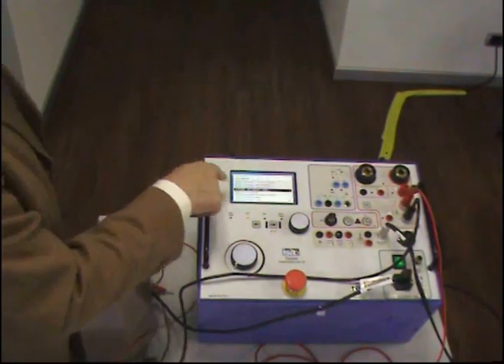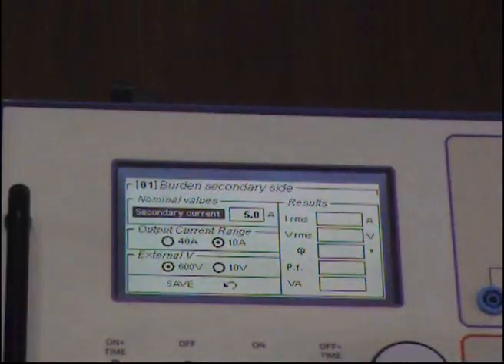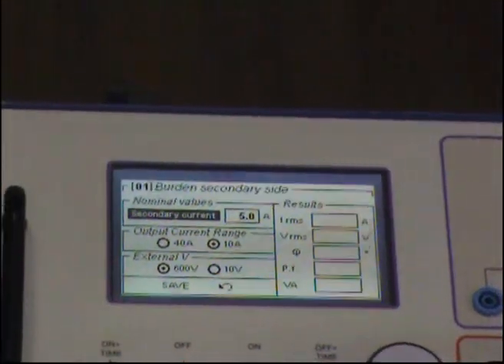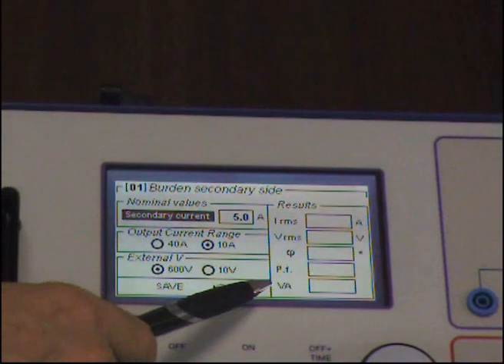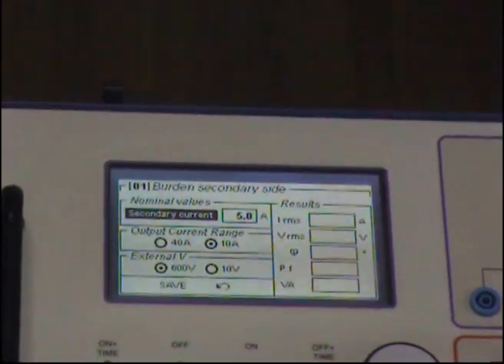Now, we're ready to go. I measure the burden and enter the selection. It is very important, firstly, that you set the current. Why? Because the volt-ampere rating — as I explained — is the resistance that we measure multiplied by the square of the current.